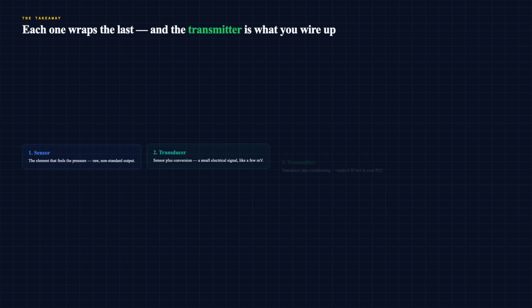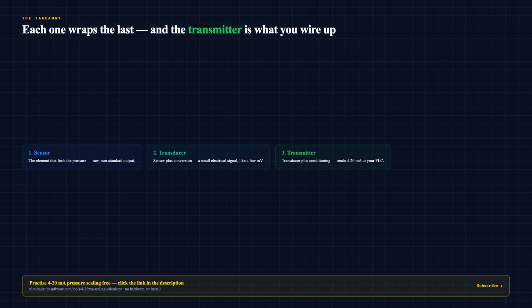So here is the chain to walk away with. A sensor is the element that feels the pressure. A transducer is that sensor plus an electrical signal. And a transmitter is that transducer plus signal conditioning, sending 4 to 20 milliamps to your PLC. Each one wraps the one below it. And the transmitter is the one you actually wire up. Get that? And the words stop tripping you up? Now go make it concrete.